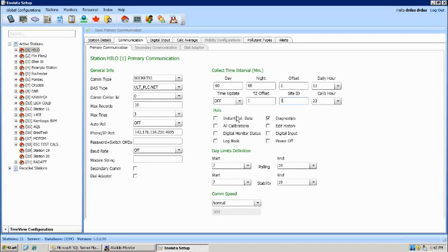In these checkboxes here, which you'll see change as we go through other protocols in a little bit, these are the different data streams that can come in. This is for Ultimate PLC polling, so this is an Envidas Ultimate data logger, and these checkboxes each mean different things. So the first one is instant calibration data, which is the 1 second, or actually the samples that occurred during calibration, not the averages, but the samples. All calibrations means that it will pull the averages from the calibrations. This is what you see when you look at a calibration report in Envista.